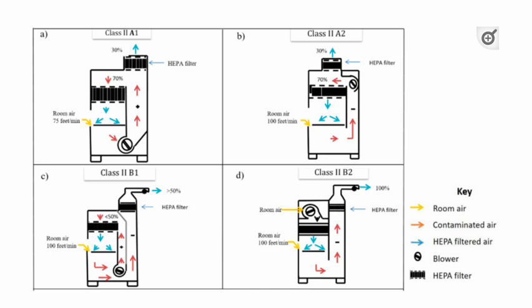Now in class 2A cabinets, please take note that when you hear type A, the exhausted air is usually exhausted in the room. Pag sinabing A, air sa room. And then for class 2B cabinets naman, usually the exhausted air is completely exhausted outside the building. It is a hard ducted type of class 2 cabinet. Again, class 2A, the air is exhausted in the room, while for class 2B, the air is exhausted using a hard duct.